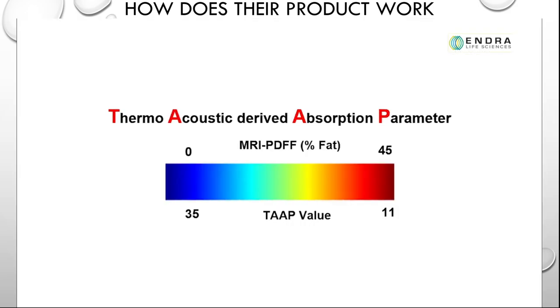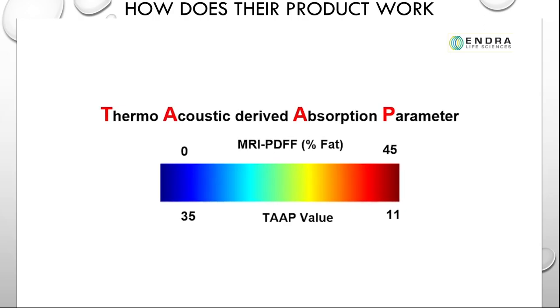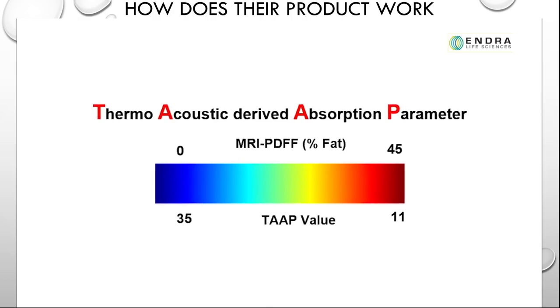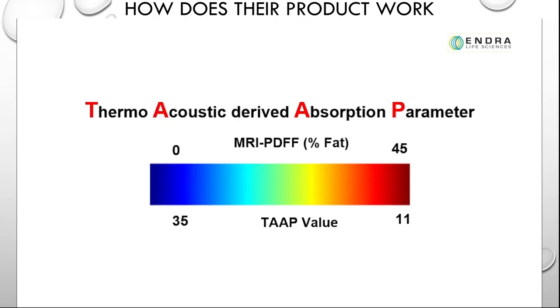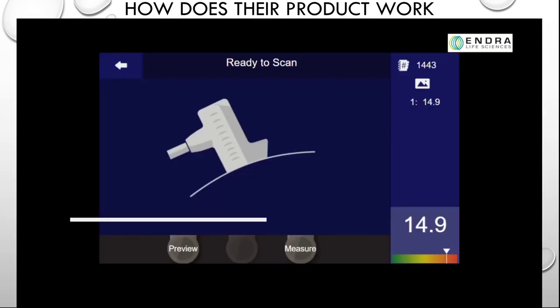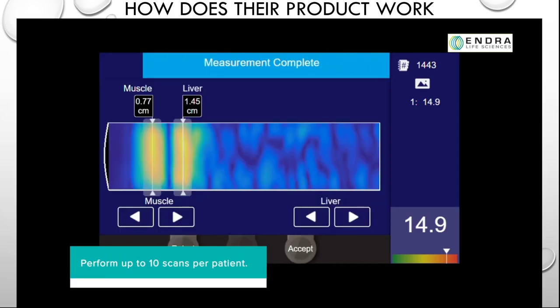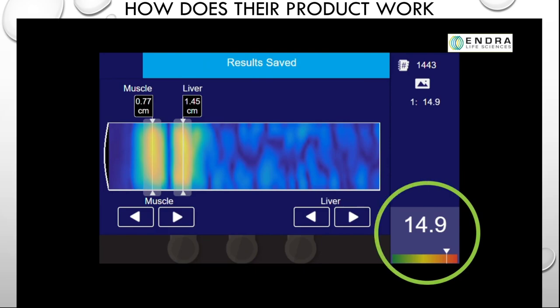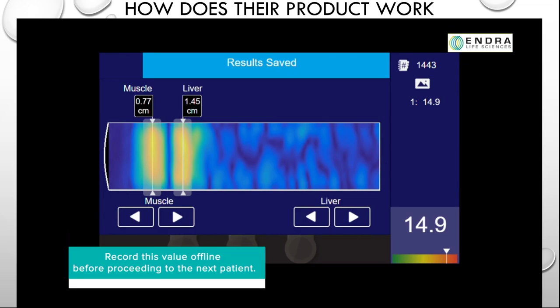Quantitative data expressed as a thermoacoustic derived absorption parameter, or TAAP, are now displayed. The parameter is derived from the two measured thermoacoustic signals and has an inverse correlation with fat fractions determined by quantitative MRI. The lower the TAAP value, the greater the degree of fat accumulation. Perform up to 10 scans per patient. Data are displayed in the right panel, as are any previous scans attained from the same patient. The average value is displayed in the bottom right corner. Record this value offline before proceeding to the next patient.